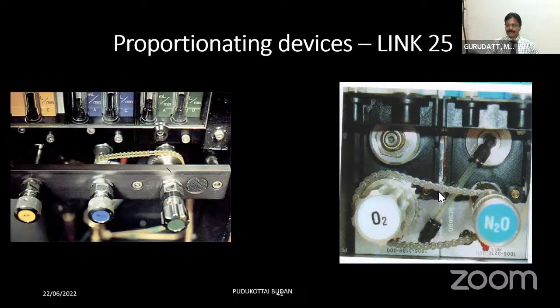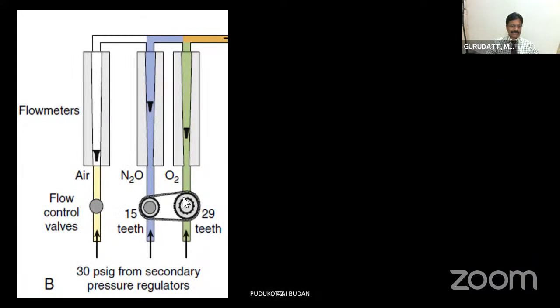Another thing you should always remember: the chain establishes a link between the sprockets of oxygen and nitrous oxide only when the oxygen falls to 25% of the total flows. Because the link gets established when the oxygen percentage comes down to 25%, this system is called the Link 25 system. I'll show you a diagrammatic representation of this. You can see here, these are the sprockets of oxygen having 29 teeth. These are the sprockets of nitrous oxide having 15 teeth. I told you 2 rotations of nitrous oxide will rotate the oxygen once, and that will maintain a ratio of nitrous oxide to oxygen of 2:1.